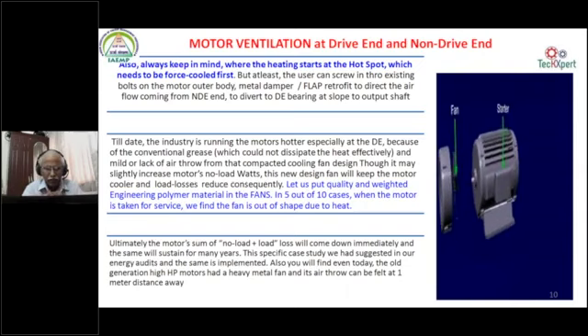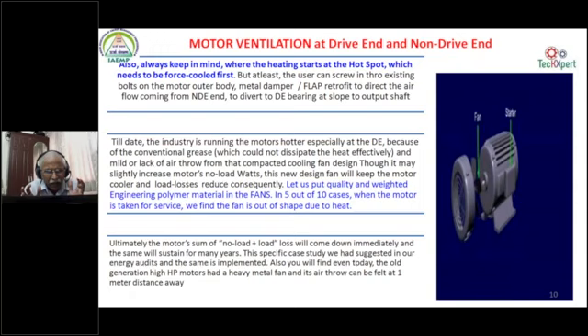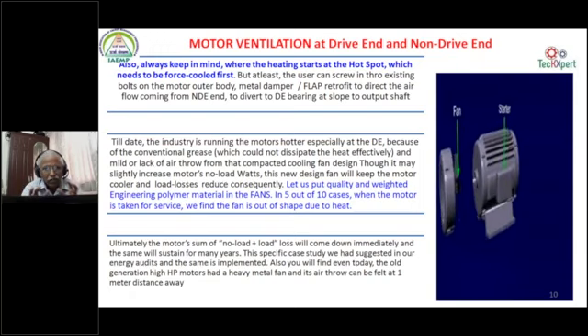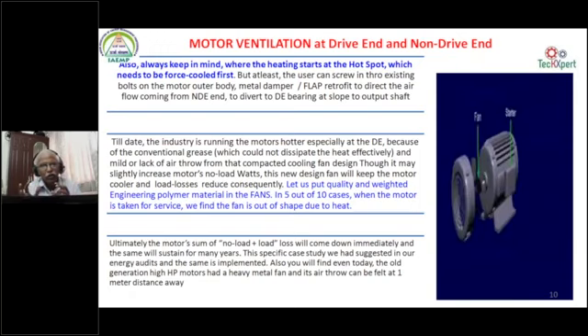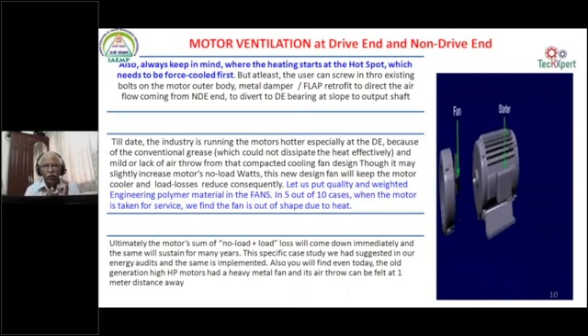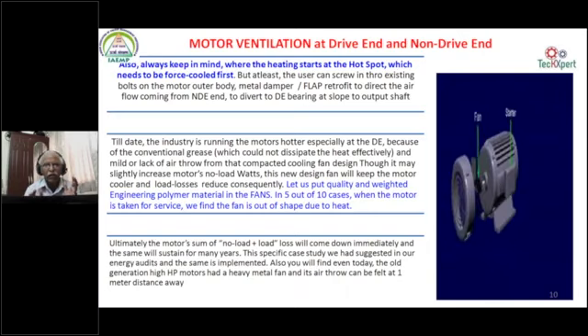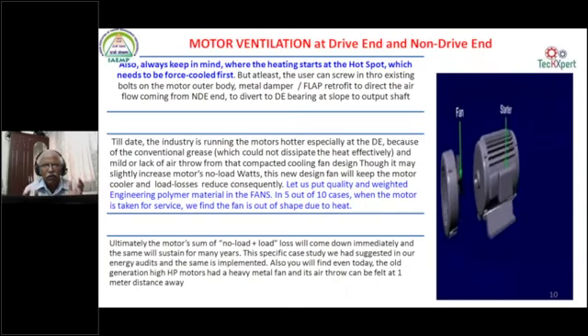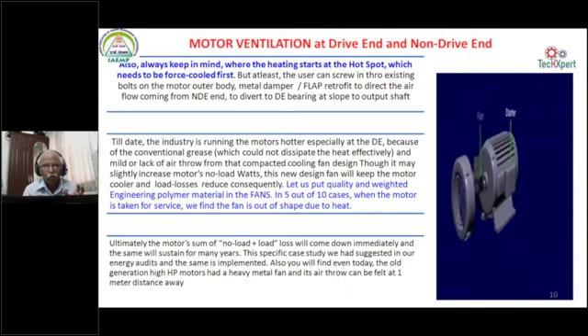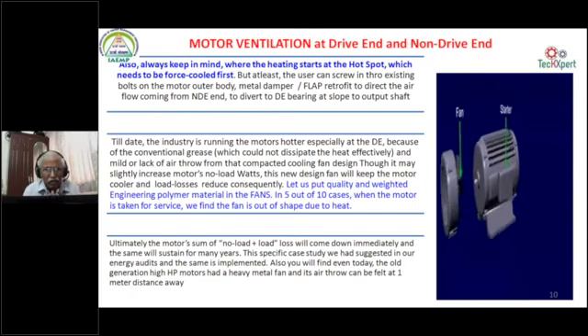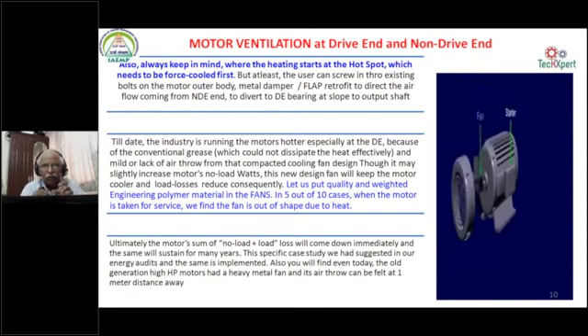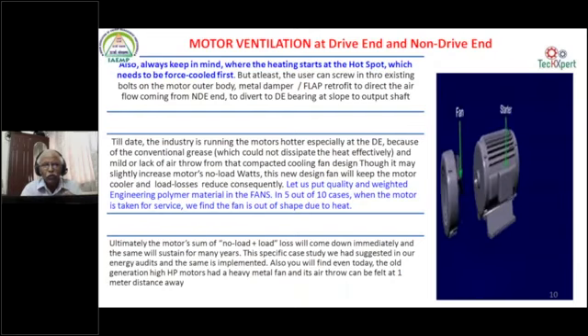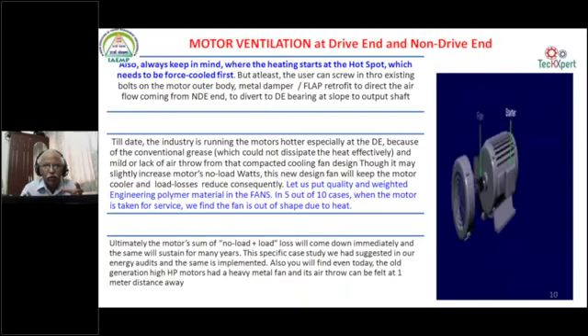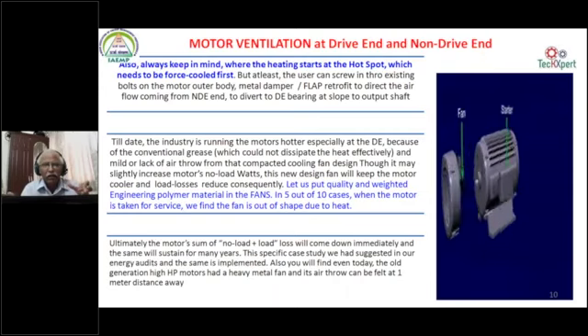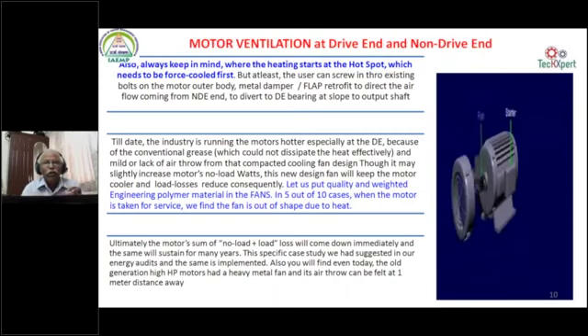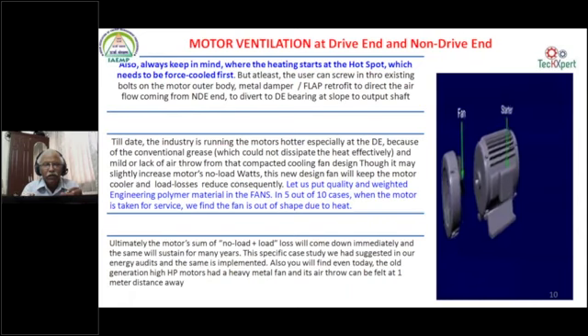So let us say the no load loss defines the motor. See, all the IE1, IE2, IE3 motor OEMs can say, sir, I want to reduce the no load loss. So to reduce the no load loss, you are putting a small fan. I don't say they have given a ready-made motor, but for our industry, you have to fine tune it with your motor. You can replace it with a higher diameter fan with more impellers so that you can get more flow across the fins of the motor.